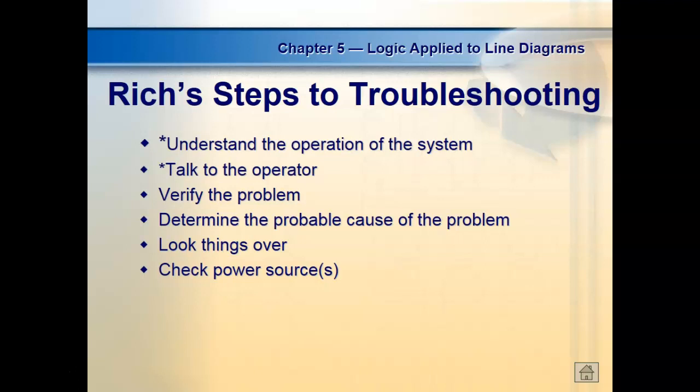Determine the probable cause of the problem. First thing we do when we've got something totally dead — if you go out there, verify the problem, and the whole system is dead — you usually verify the source first: is it getting power to the system? One of the first labs we're going to do is open up the disconnect and you're going to verify the power with the meter. This thing has a master control relay in it.